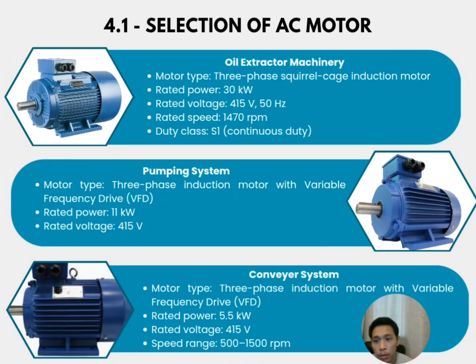The first one is the oil extractor machinery. For this high demand application, we have selected a 3-phase squirrel cage induction motor, which I have told you before. For the performance, it delivers a rated power of 30 kilowatts, making it the most powerful unit in this group. For the electrical specification, it operates at 415 volts at 50 Hz with a rated speed of 1470 RPM. For the key detail, notice it shows the S1 duty class. This means the motor is designed for continuous duty, allowing it to run at a constant load for long periods without reaching thermal instability. This is essential for steady oil extraction processes.